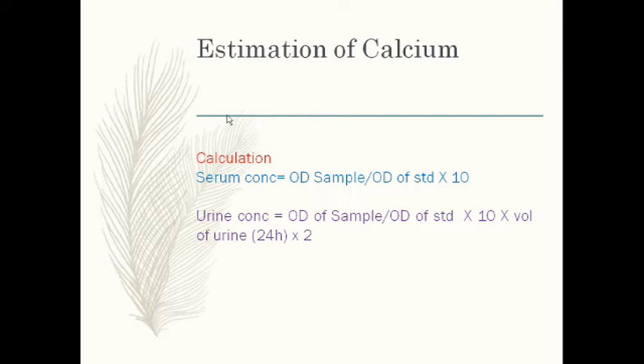Coming to the linearity, using the Arsenazo III method you can calculate serum calcium up to 16 milligram per deciliter. What if the patient has a 20 mg concentration in his body? The machine has a linearity of 16 only. The machine cannot detect above 16. What will you do in that case? What technique are you going to use? I don't have any other new instrument with more linearity, nor any other alternative lab to go to, but the patient has more than 16 calcium concentration. With the same sample I want to estimate. So how will you do that?